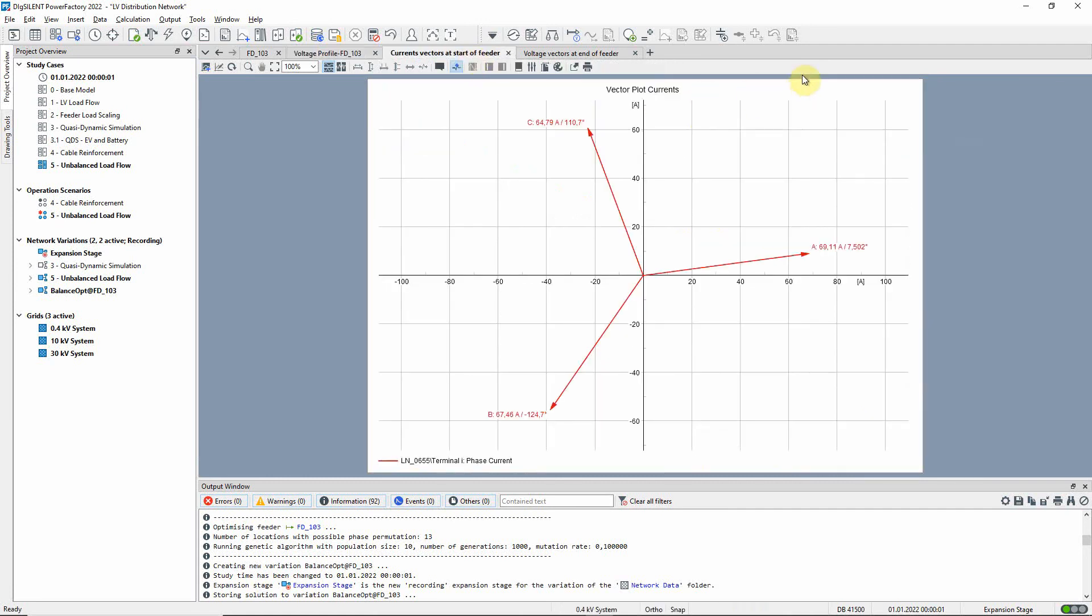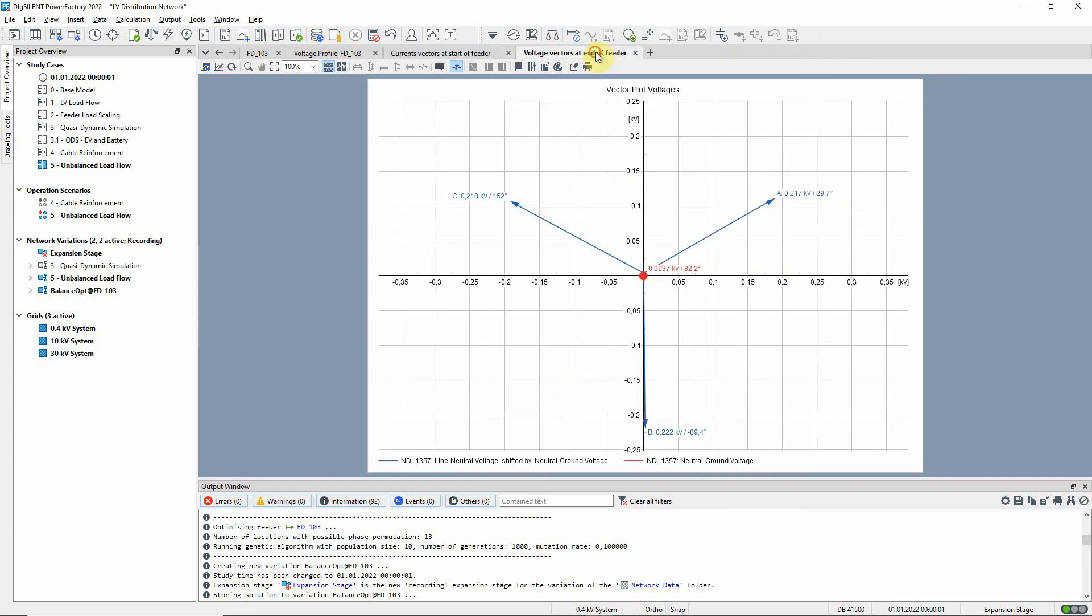Looking at the current vector plot, a more symmetrical system is seen. And in the voltage vector plot, we can see that as a result of the phase balance, the neutral to earth voltage is reduced too.